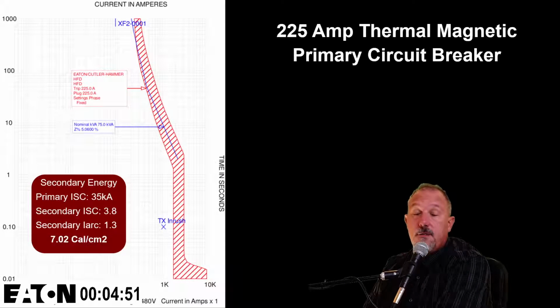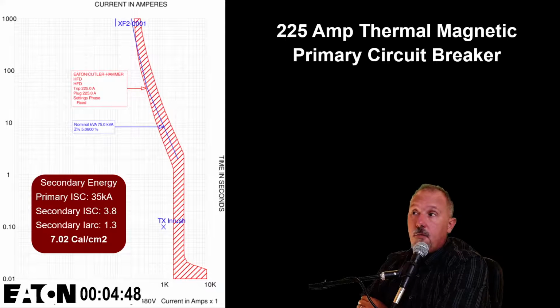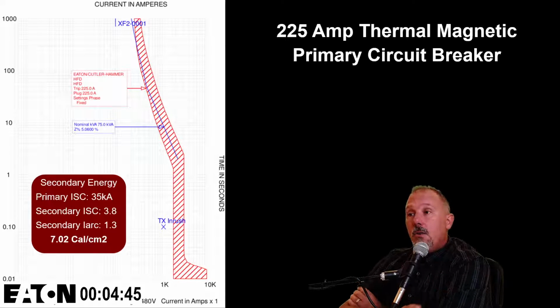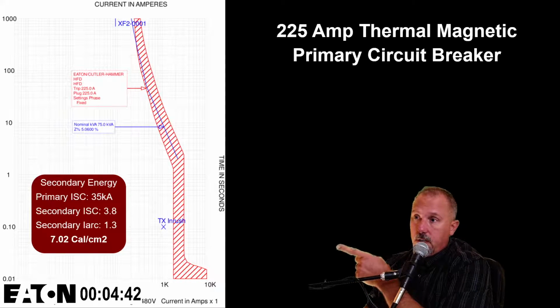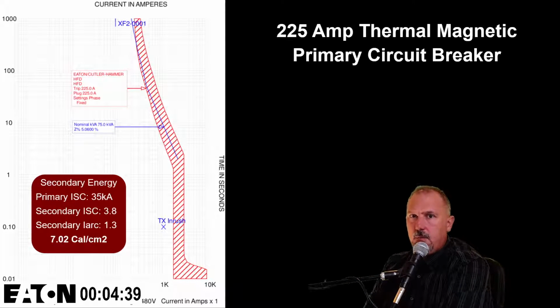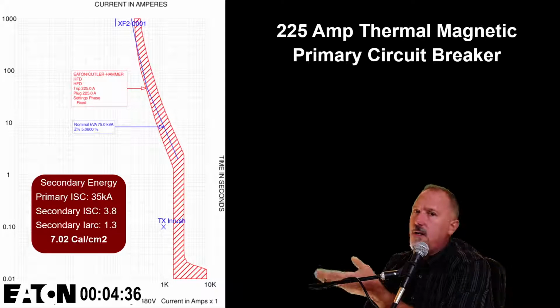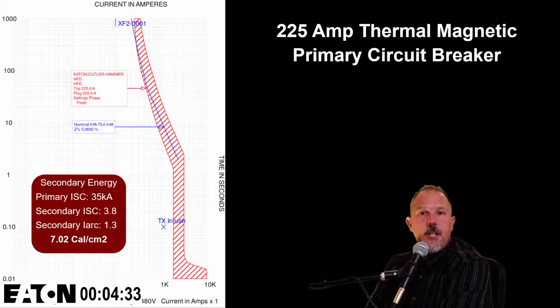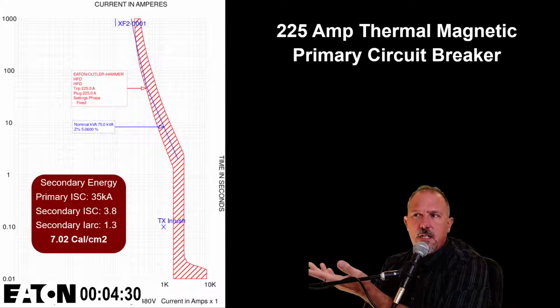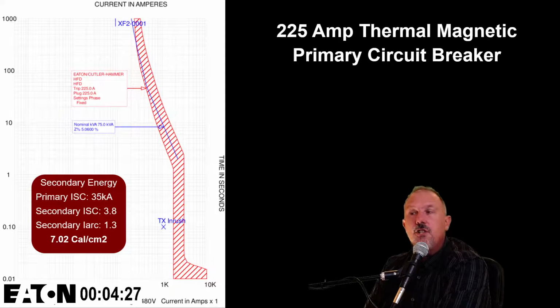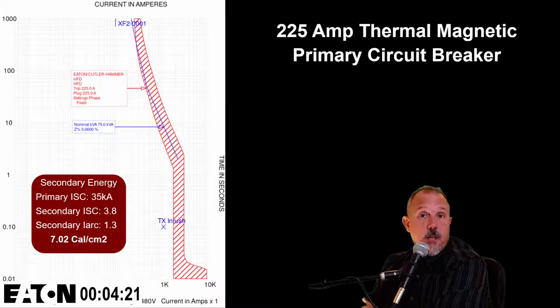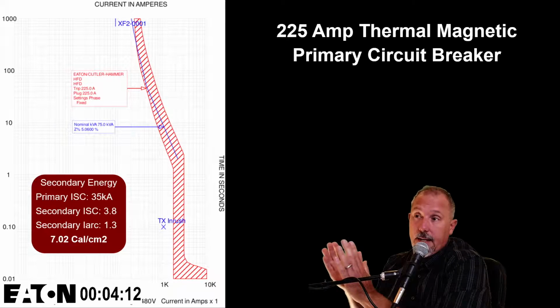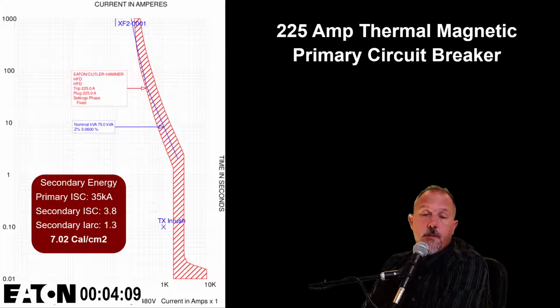Well, let's take a look at a time current characteristic curve. This is a 225 amp thermal magnetic circuit breaker. Also, you'll see that I have the inrush current marked there, and I believe that's about 12 times. I was just on a call this morning, and one of my application engineers within Eaton says he'll typically use around 8 times for inrush at these size dry type transformers. You can sometimes get that information directly from the manufacturer. I used 12 times in this case. I probably could have, and maybe arguably should have, done the 8 times as well, but I didn't. In any case, that's around 12 times your full load amps from an inrush perspective.